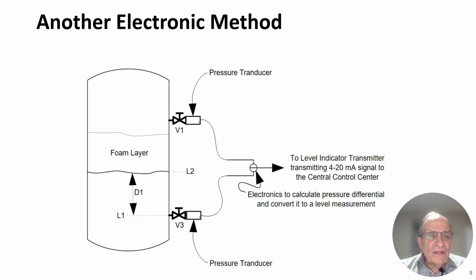Another method of using electronics to indicate the level in a vessel would be to put a transducer on both taps. Transducer on the top tap, a transducer on the bottom tap, taking the electronic signal that comes off these transducers and converting it to a 4 to 20 milliamp signal that goes to control center. Now you may wonder why we use a 4 to 20 milliamp signal and not a 0 to 20 milliamp signal? Well, being that a 4 shows for 0 level and a 20 shows for maximum scale level is a very good way of being certain that the equipment is actually working.